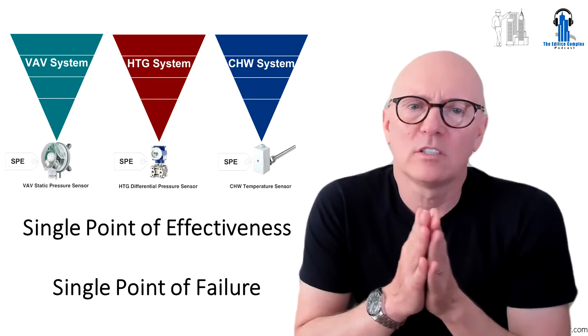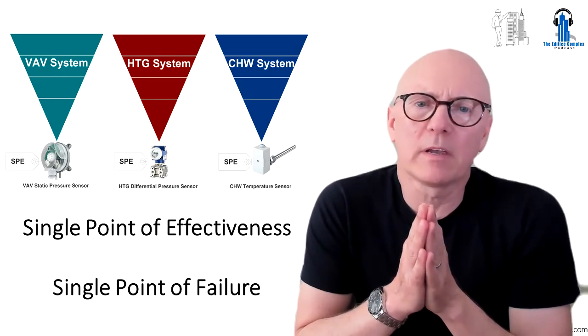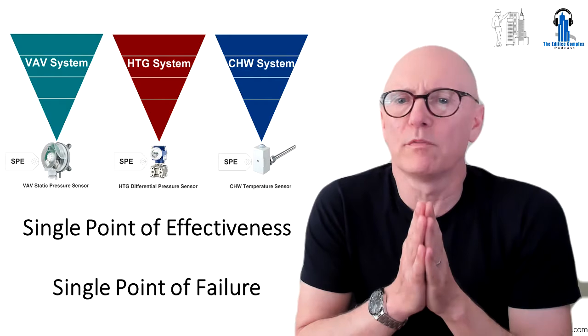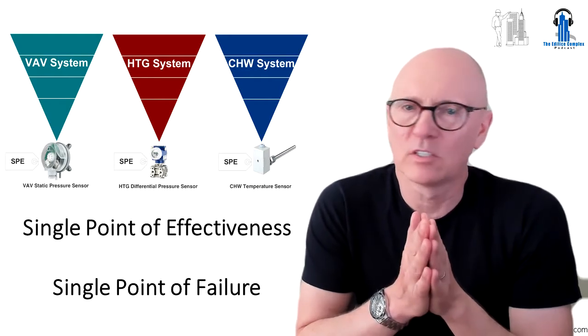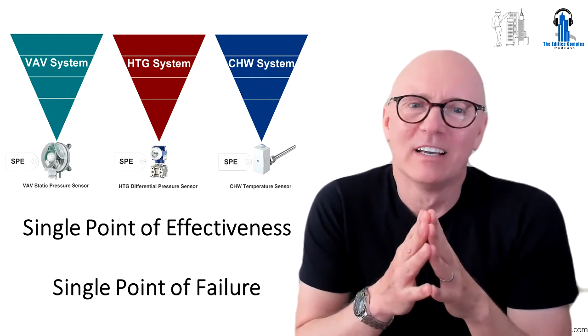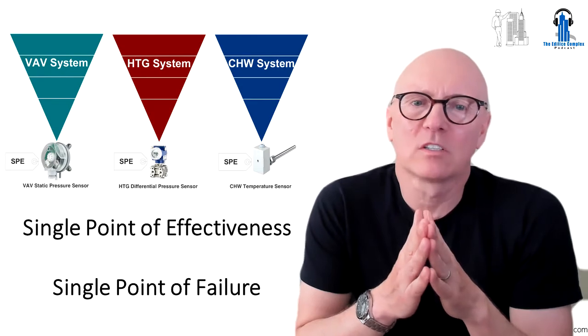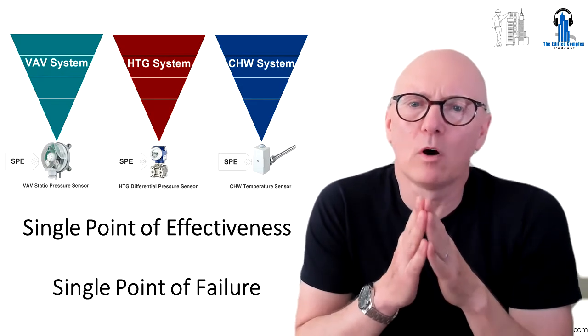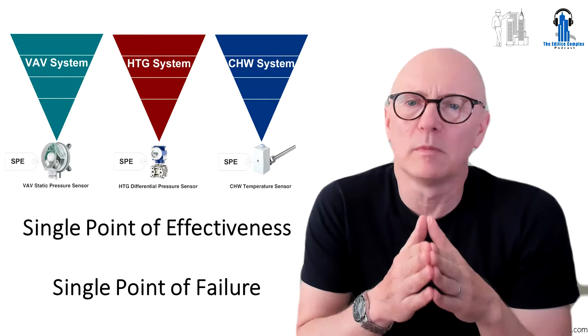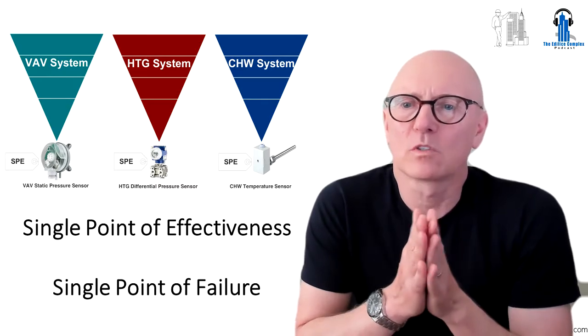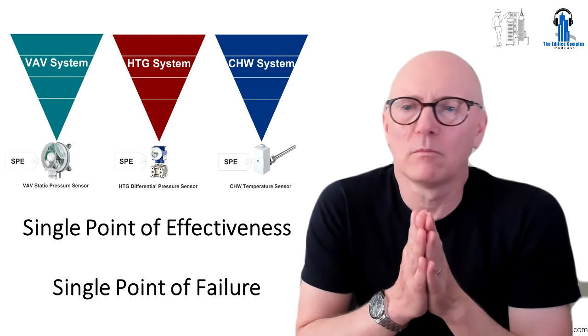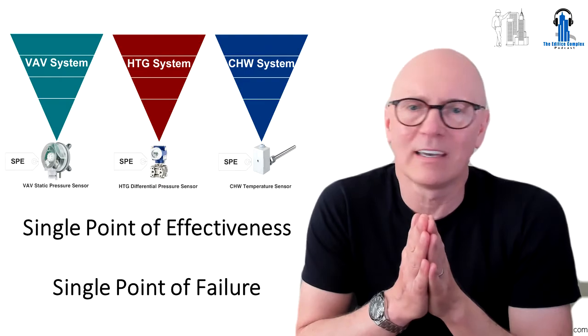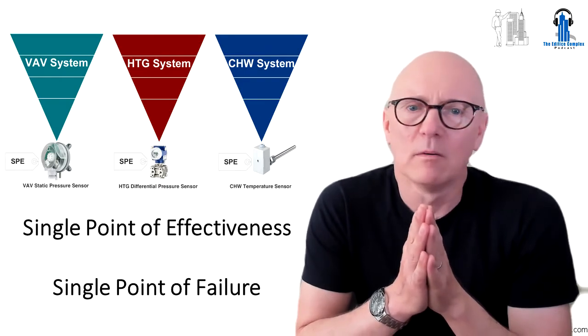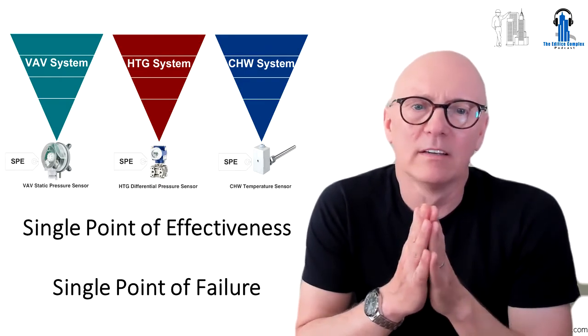Two, energy modeling assumes all MEP and facade systems are installed and performed impeccably. This is certainly not my lived experience. And number three, energy modeling assumes optimum operating control set points are determined and set. Plus, the control system has been tuned during early occupancy. Again, this is most definitely not my lived experience in any way.